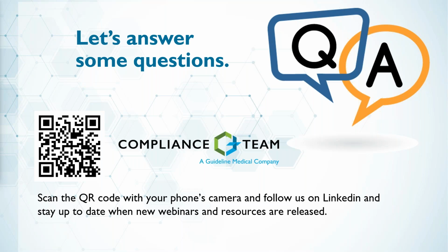I have worked on, at least in the medical device side, depending on the nature of the complaint and depending on the severity and whether we already understand what the root causes are, like if that issue has been investigated previously and we understand that the severity is low, you can potentially do some kind of a closure on the complaints based on that known understanding.